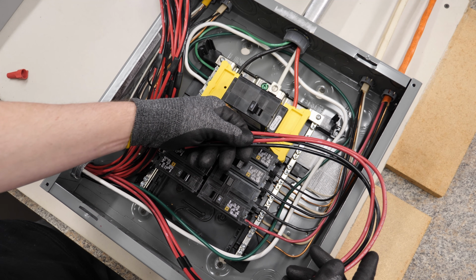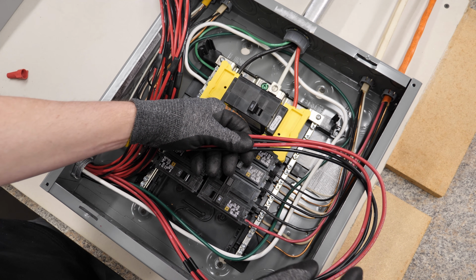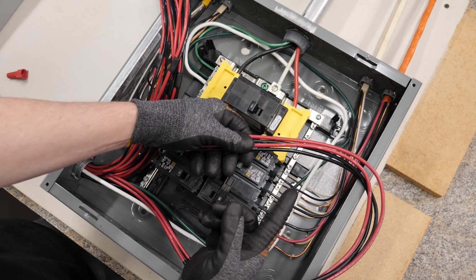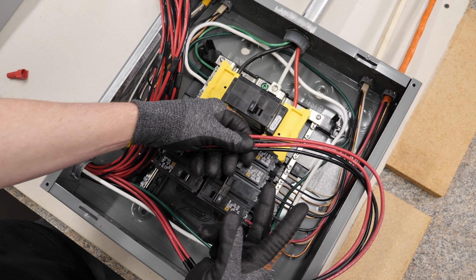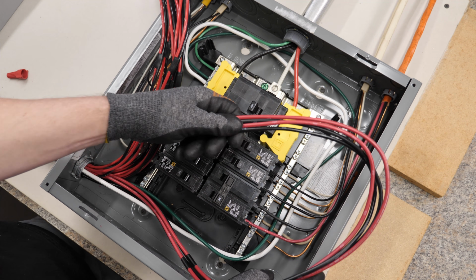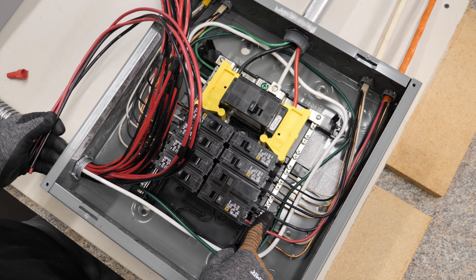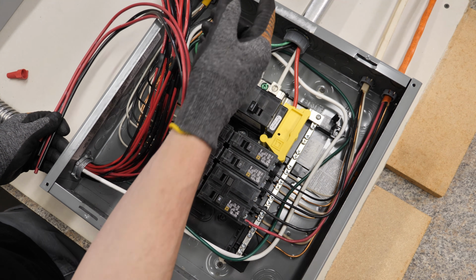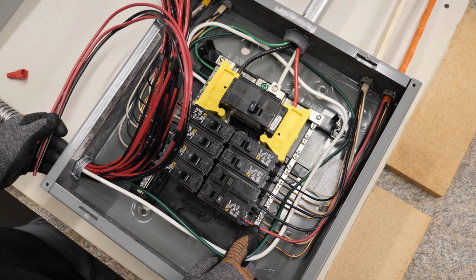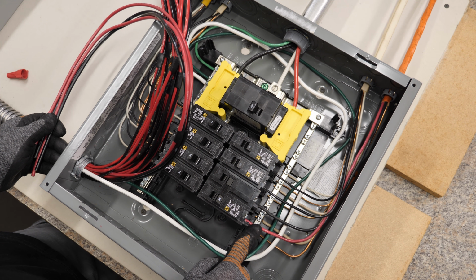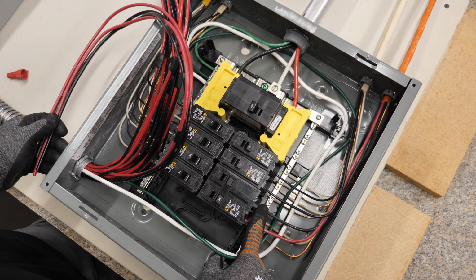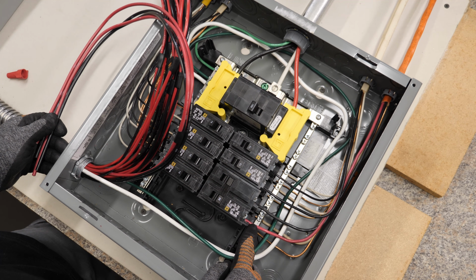I found my red and black A and B wires. A is phase 1, or L1. B is phase 2, or L2. Inside your panel, the black wire up here is L1, and red is typically L2. So A wires go to this portion of the circuit breaker, and B, or L2, goes to the red wires.